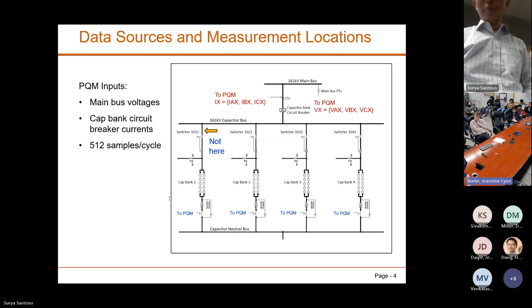So that is the data source where we got the data. Now I'm going to explain what the design of the capacitor bank looks like. This is a one-line diagram, but here is a three-line diagram, meaning you will see the A phase, B phase, and C phase. This is the A phase bank. It is made up of two parallel strings, and in each parallel string you can find 5 capacitor units connected in series.